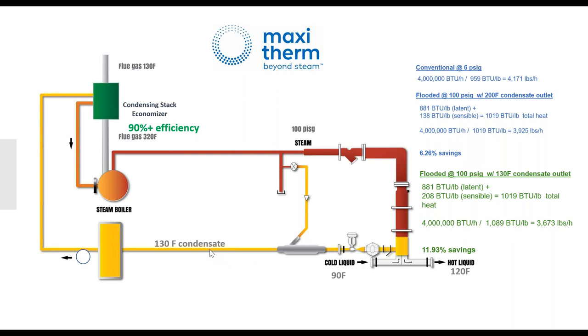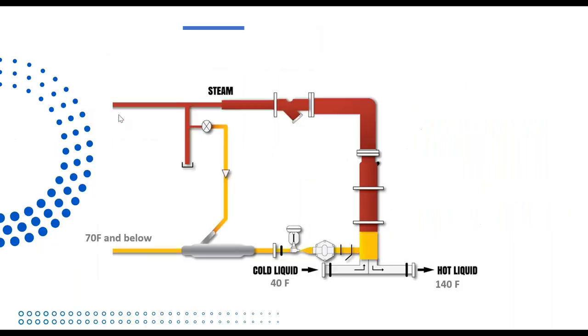And then you bring back condensate to increase the boiler efficiency. Of course, you can have a two-stage economizer, with a first stage for feeding the boiler to preheat the water, and a condensing stack economizer. We're not going to cover this in detail today, but we're working on another webinar about the 100% closed loop and condensing stack economizer.